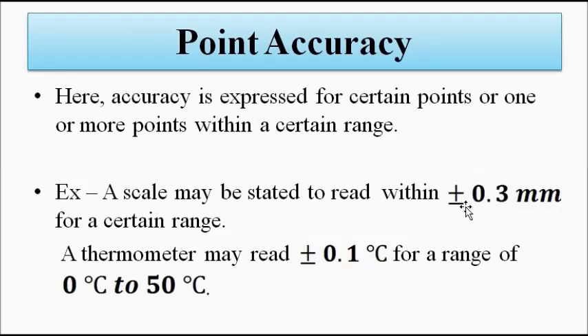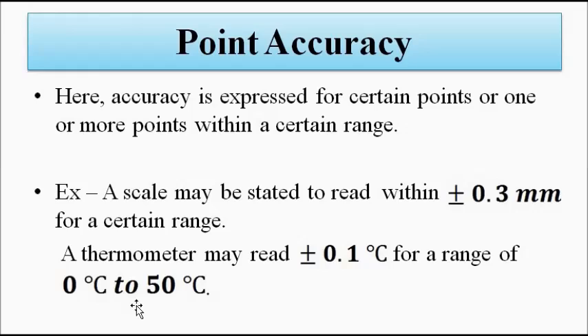For a range of 30 to 50 millimeters, whatever reading we get, there is a chance that the actual output is that reading plus or minus 0.3. Similarly, a thermometer can be specified to read plus or minus 0.1 degree Celsius for a range from 0 to 50 degrees Celsius. For example, when the output reading is 30°C, there is a chance it is actually 30.1°C or 29.9°C. That is what point accuracy means.